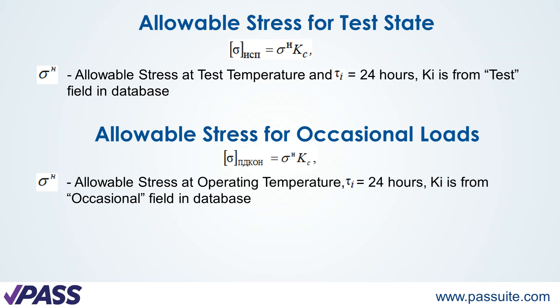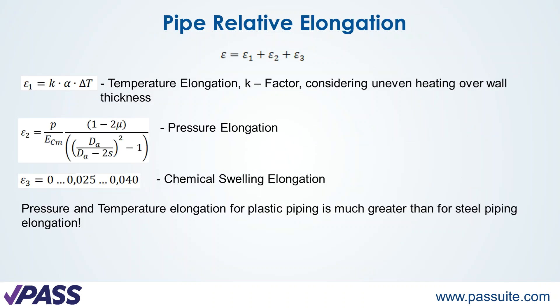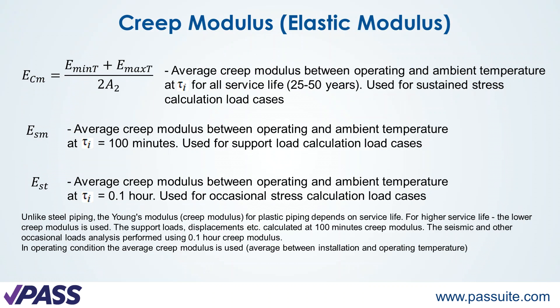The pipe elongation depends on three factors. The first factor is elongation caused by temperature expansion — for plastic material, this elongation is about 10 times greater than for steel piping. The second part is elongation under internal pressure, and the third part is elongation caused by chemical swelling.